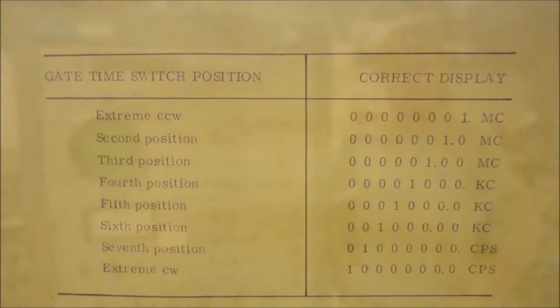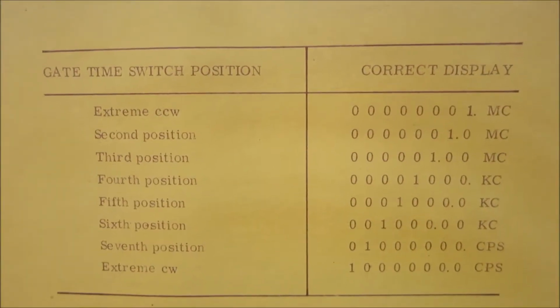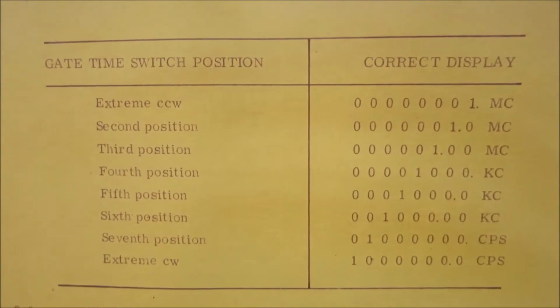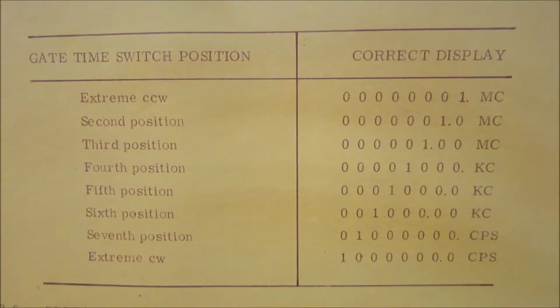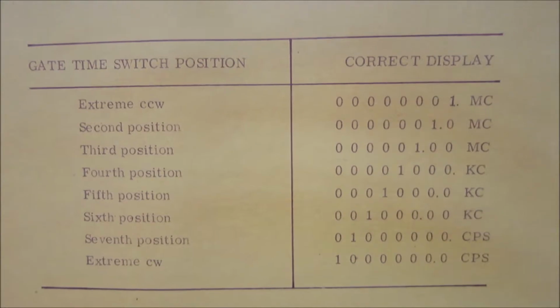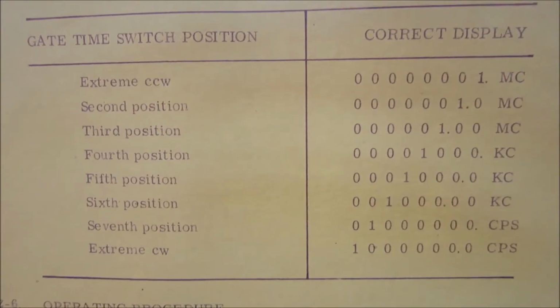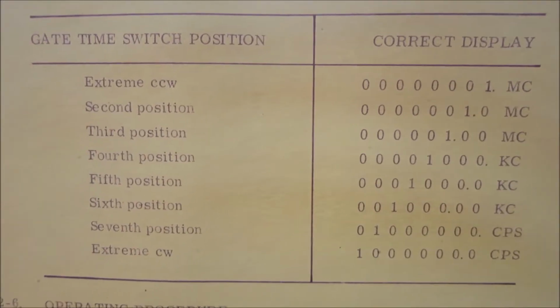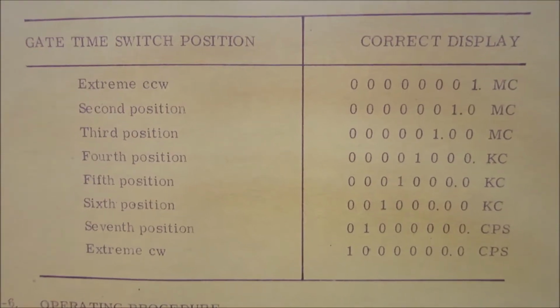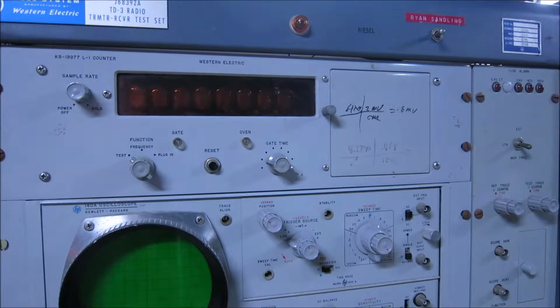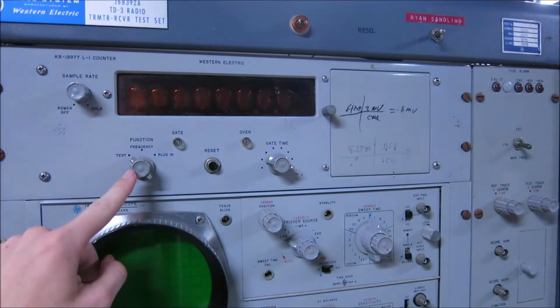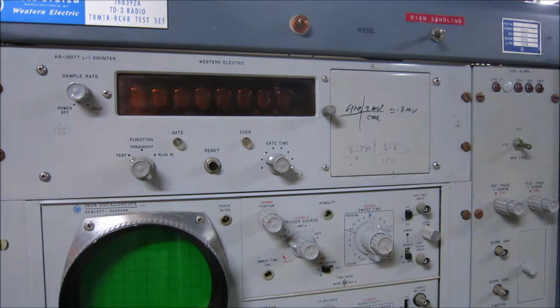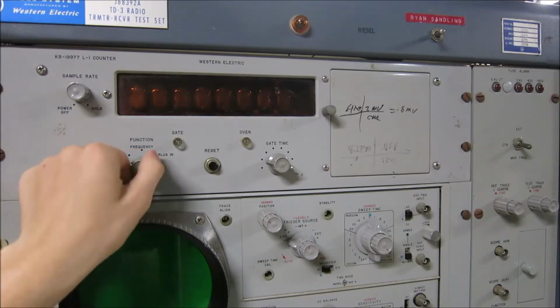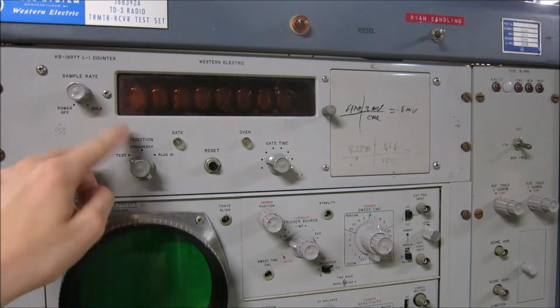With all equipment it should come with a manual. Here I have the manual for this frequency counter, and as you can see there are two tables on this page. These two tables allow us to test this unit with its built-in test calibration setting. On the machine itself we have a function switch, which allows us to change what functionality the machine is set for. It has frequency, plug-in, and test, and we're going to use the test setting.